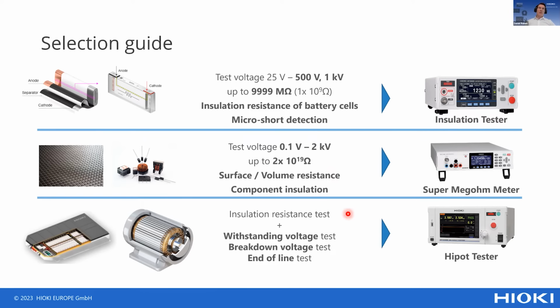As a third category, we have withstanding testers, also in combination with insulation resistance tester. So not any longer looking at cell level, but looking at pack and module. Here, it's the safety test to understand at which level you might have a breakdown. This is especially interesting for type class testing, or you have the end of line testing where you need to apply a much higher voltage.